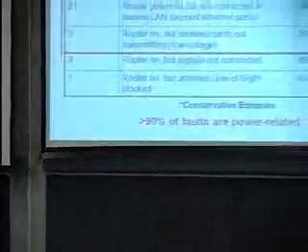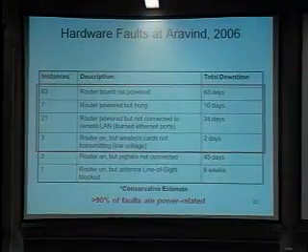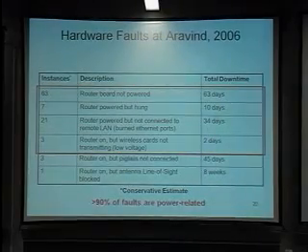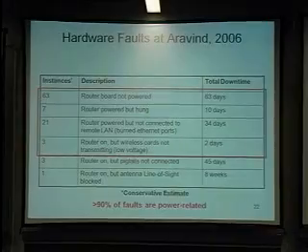So we've had this system up for a couple of years now, and we can kind of understand why it fails when it fails. I'm not going to go through all of these, but one obvious observation that came out is that almost all failures were power related. 90% of the failures, we kept a log of why things broke, and the answer is power most of the time. And I'll walk through the reasons.